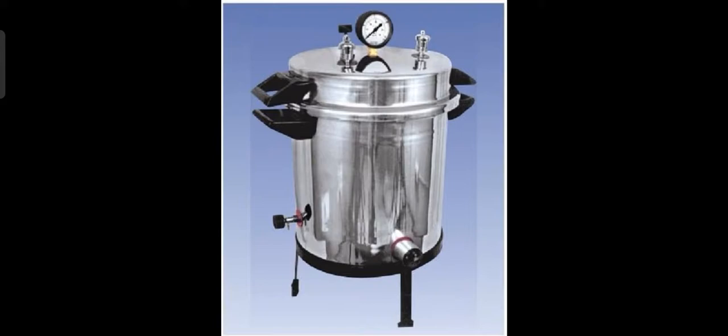What is the procedure? Sufficient amount of water is placed inside the autoclave. The material is placed inside the autoclave for sterilization. The cotton plug should be covered with a piece of butter paper so that the plug doesn't get wet. The lid of autoclave should be tightened with the help of screws. Then switch on the plug. The steam outlet is kept open till we feel that the air from inside the autoclave has been evacuated, and then close the steam outlet.